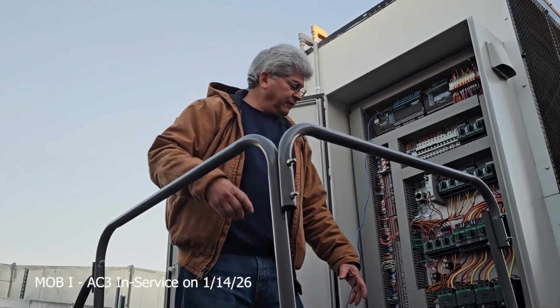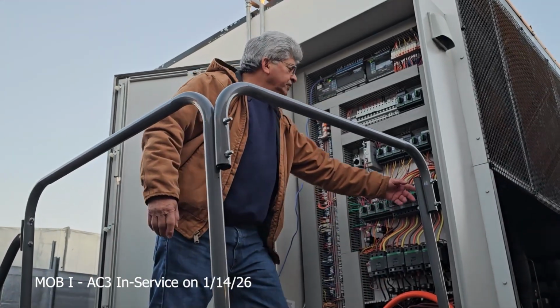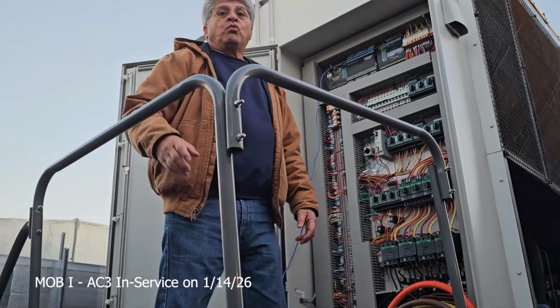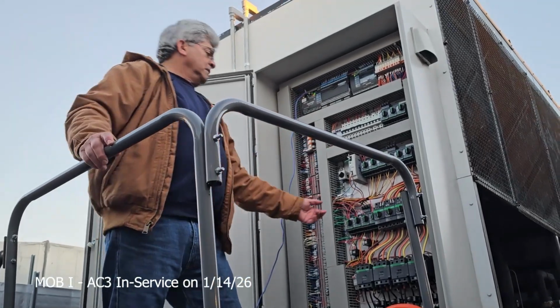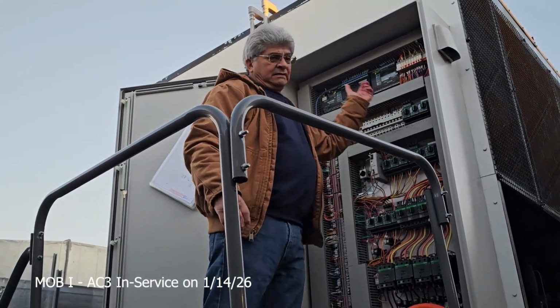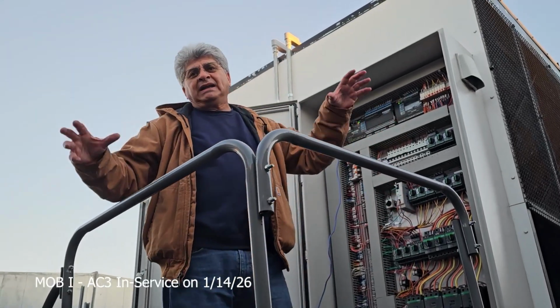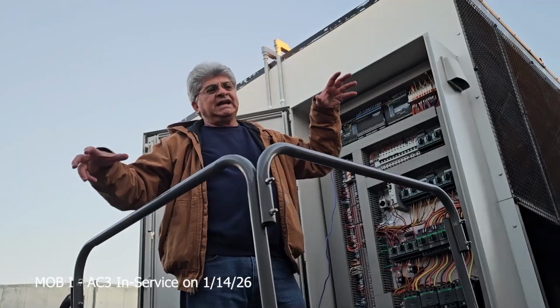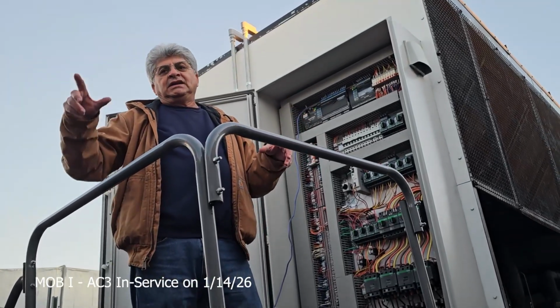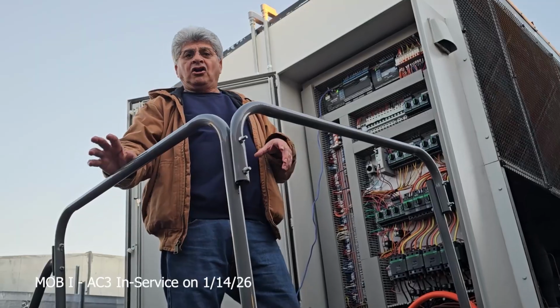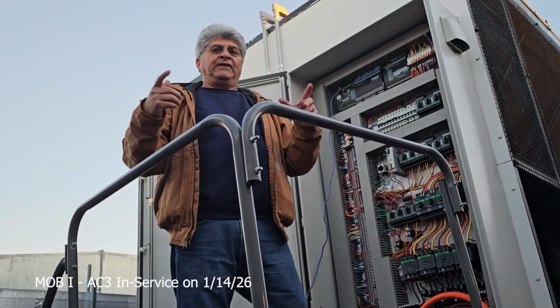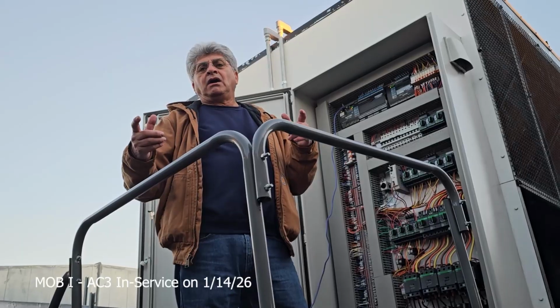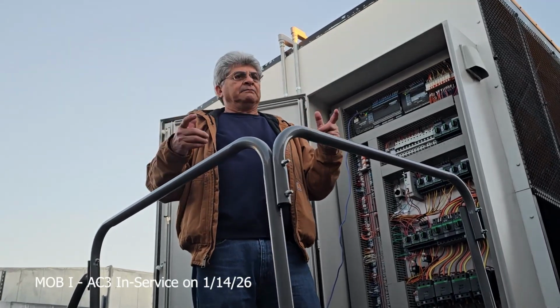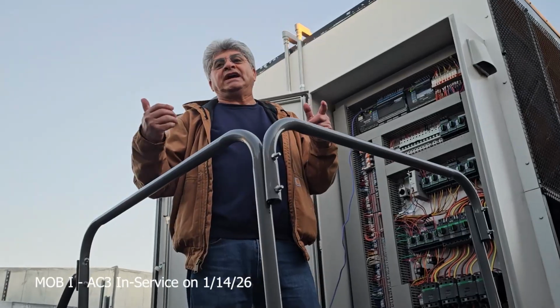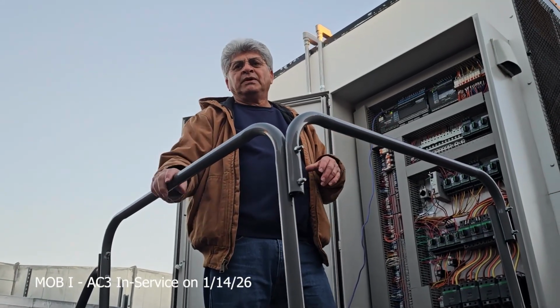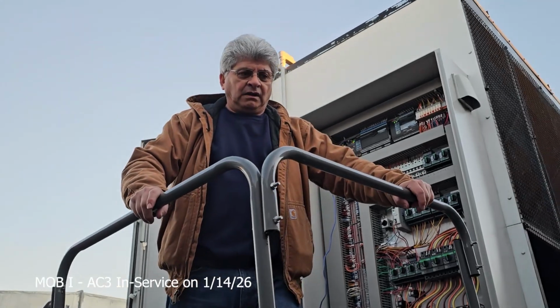Here, you shut that off. That shuts your incoming power. All these are turned off. When you're going to power your unit back on, turn all these on. Your fans, if they see an imbalance, if they see one fan running and another fan not running, it's going to sense an imbalance and throw an alarm. You won't see that alarm. It's going to be internal to the fan, and the fan's going to decide. It's not going to be a hard shutdown. It's going to say, hey, maybe I've got another fan that hasn't come online yet. So we'll try several times before something turns into a hard reset.